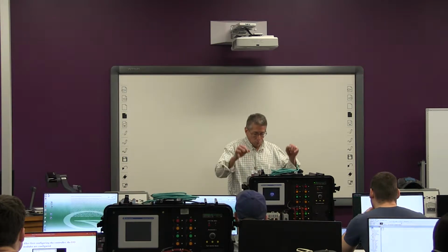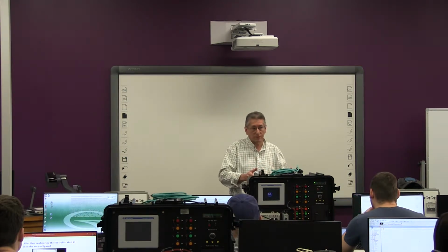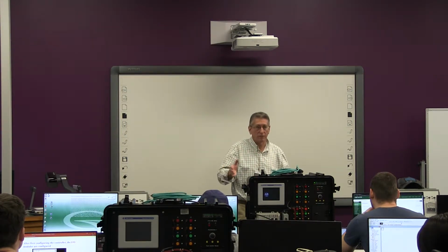So we have to use that addressing for the PLC to even know what it is. I know some of you have dropped in an XIC instruction, and I've seen this before, and you might just put a word on it or a symbol like binary. But then it errors out on you, doesn't it? Because it says this is not an address. So you have to use those addresses that are hard-coded in the memory of the PLC.